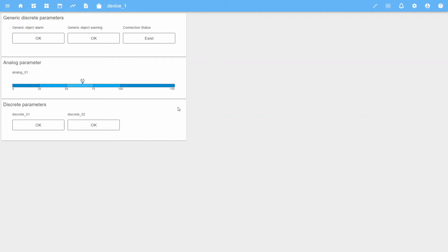They are triggered when any of the device parameters goes into an alarm or warning state. Let's start with discrete parameters. Only one alert can be generated for discrete parameters. An alarm alert will be generated if the alarm parameter type is specified, and a warning alert will be generated if the warning parameter type is specified. discrete_01 has an alarm parameter type and discrete_02 has a warning parameter type. Let's simulate their active state.